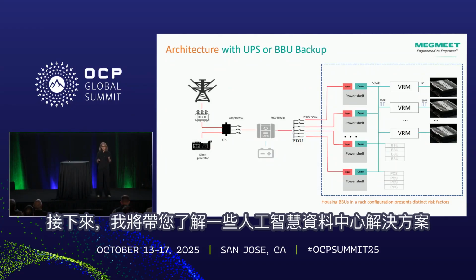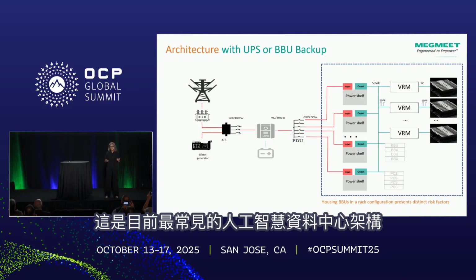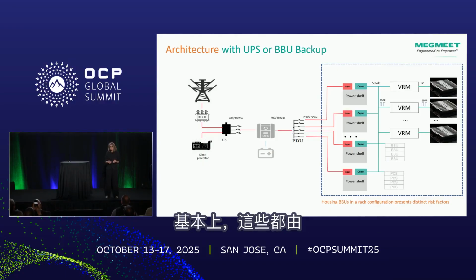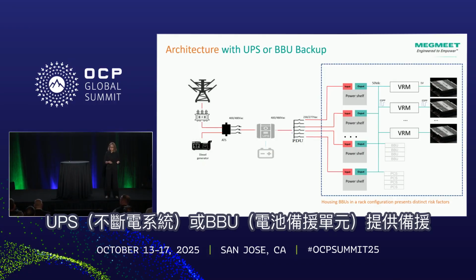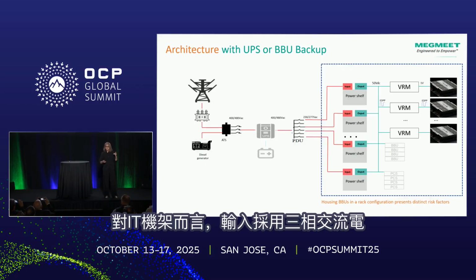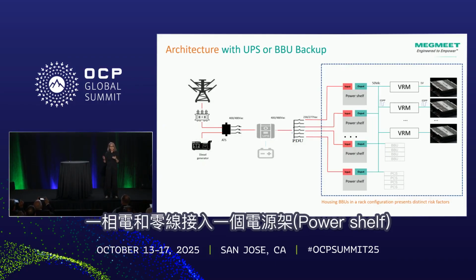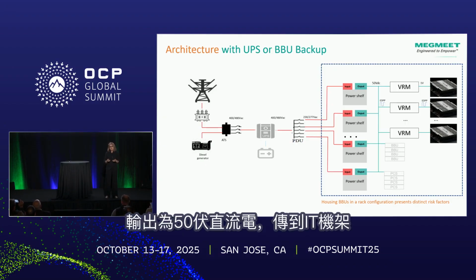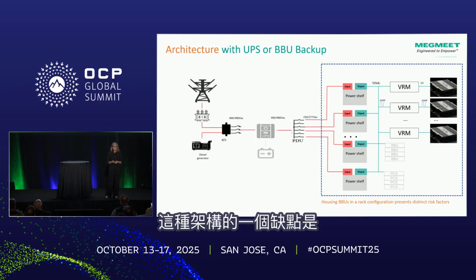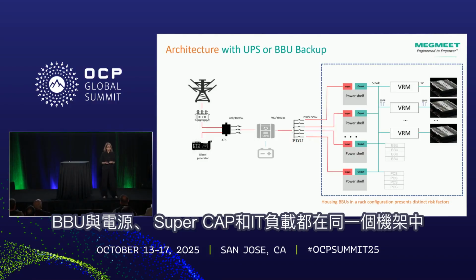So I'm going to walk you through some of the AI data center solutions that today you see the architecture. This is the main or most common AI data center architecture that you see today. Basically, these are all backed up with UPS or BBU. A 3-phase AC when it comes to the IT rack. The 1-phase and neutral comes into each power shelf, and the output is 50 volts DC, and that is distributed to the IT rack. There is one downside to this architecture, and that is the BBU, that is the battery backup, is in the same rack as the power and the Super Cap and the IT load, and everything is in the same rack.